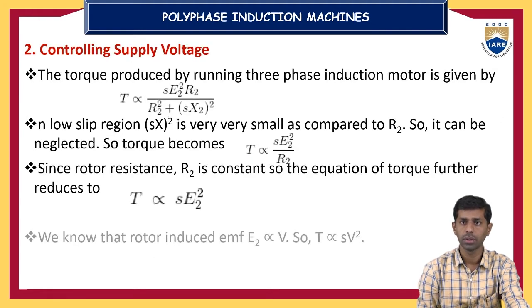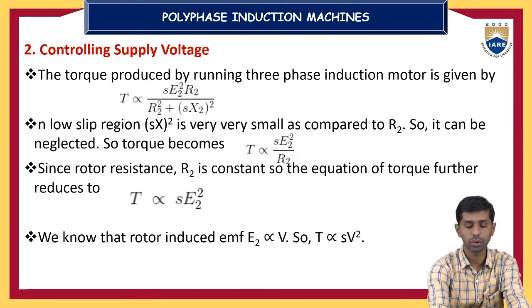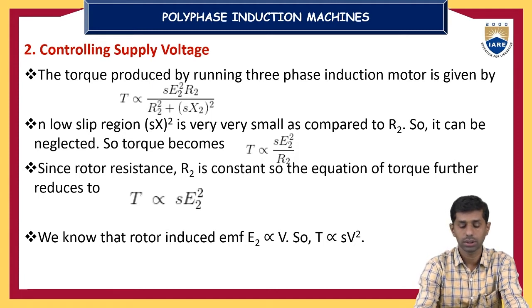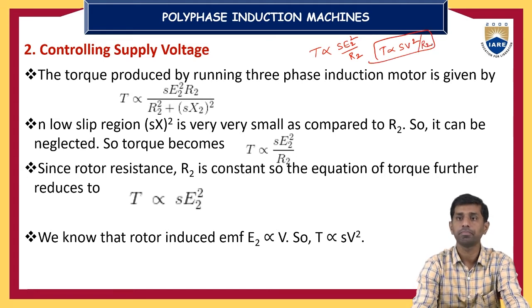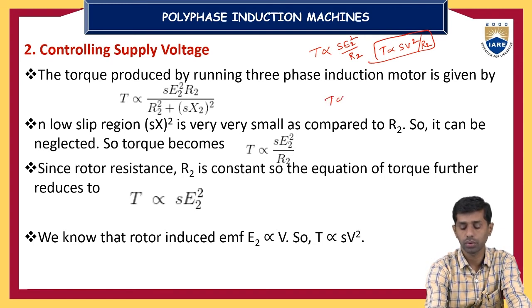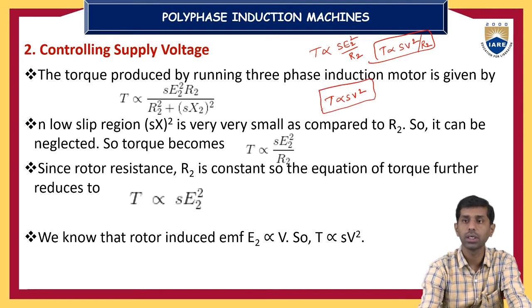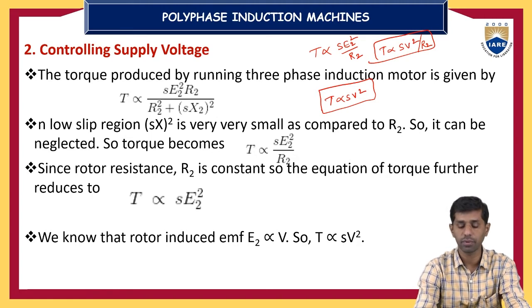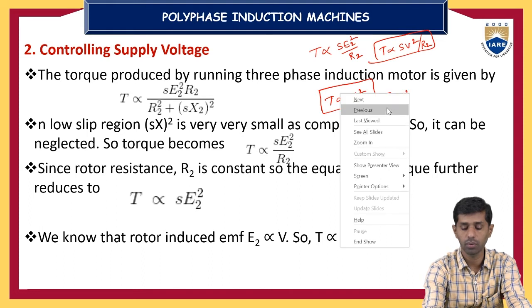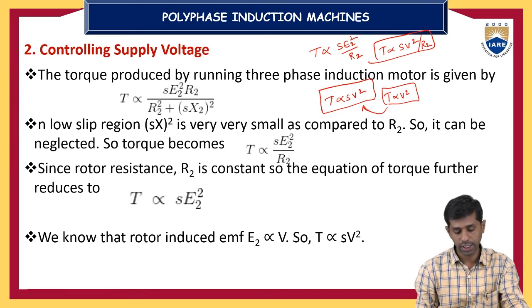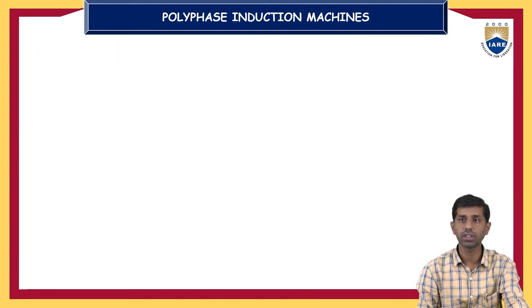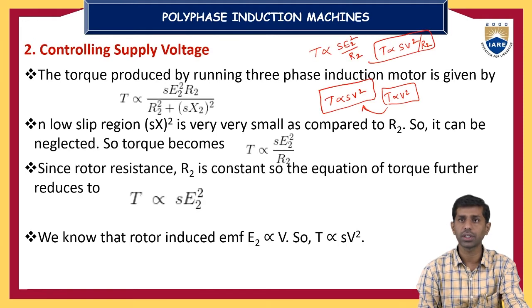Another method is controlling the supply voltage. We know the torque relation: torque is proportional to slip times the square of induced EMF in the rotor divided by R2, which can be written as torque proportional to s × V² / R2, since E2 is proportional to V. Torque is very sensitive to changes in supply voltage. At the time of starting, torque is proportional to V². So by changing the supply voltage, we can effectively change the speed of the induction motor.